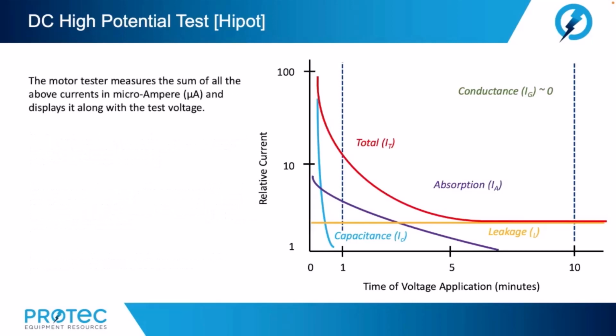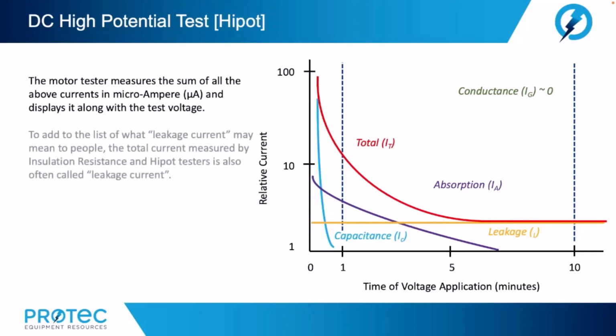The motor tester measures the sum of all the above currents in microamperes and displays it along with the test voltage. To add to the list of what leakage current may mean to people, the total current measured by insulation resistance and high potential testers is also often called simply leakage current. IEEE 95 calls this the measured current.